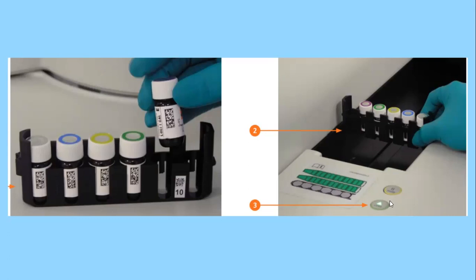There's a little pause button and a go button. If the green is flashing, that means you're able to put reagents on, and you just click that button and it will send it into the machine. It takes a minute for the machine to read the barcodes and to put it on in rotation, but then anything else that the machine needs, it will pop up on the screen. If all needs are met, they will just disappear.